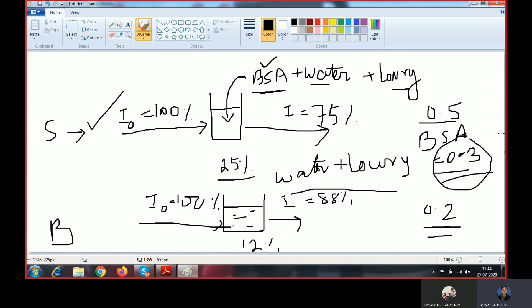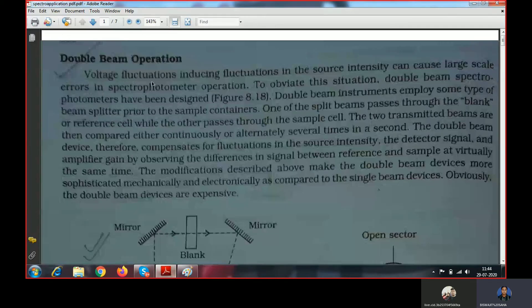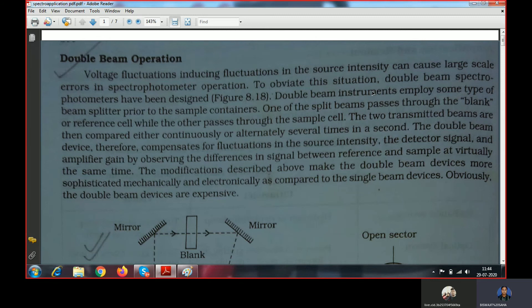This is the reason why we need a double beam spectrophotometer — so that simultaneously we are transferring light through the blank and through the sample. Voltage fluctuation inducing fluctuation in the source intensity can cause large-scale errors in spectrophotometer operation. To overcome this situation, double beam spectrophotometers have been designed.